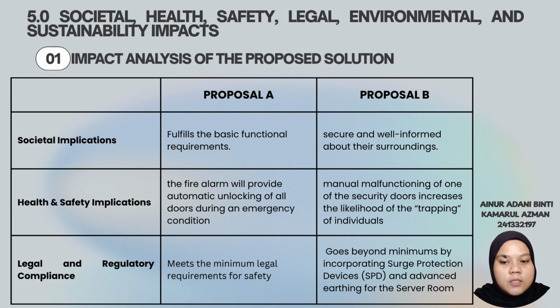For health and safety implication, for Proposal A, the fire alarm will provide automatic unlocking of all doors during an emergency condition, while for Proposal B, manual malfunctioning of one of the security doors increases the likelihood of the trapping of individuals. Legal and regulatory compliance. Proposal A meets the minimum legal requirements for safety, while Proposal B goes beyond minimums by incorporating surge protection devices and advanced earthing for the server room.